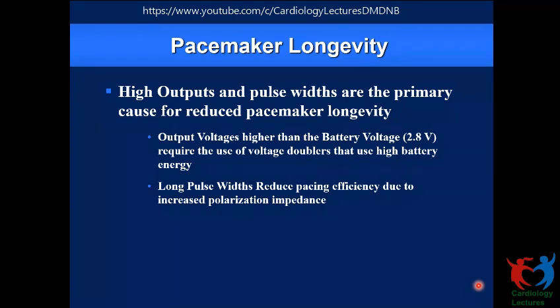The chronaxy point, if you have to go into real detail to find it, is this: first find the threshold at infinite pulse width. The maximum pulse width is 2 milliseconds. What is the threshold? Assume you find the threshold at around 0.6 at 2 pulse width. Then you double that to 1.2, and as you reduce the pulse width, at the point where it loses capture, that point becomes the chronaxy point. But that is only if you really want to find out. For clinical relevance, it really doesn't count so much.